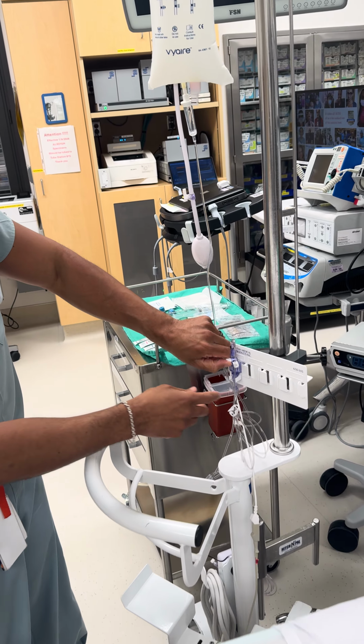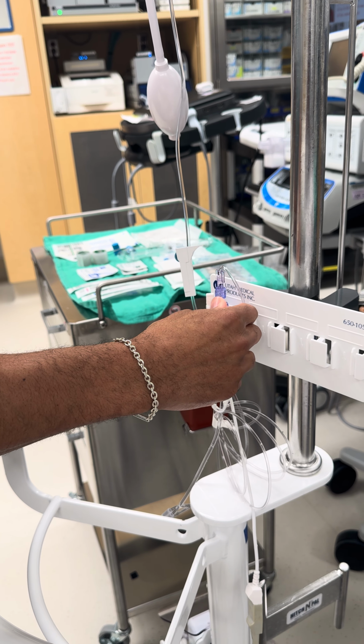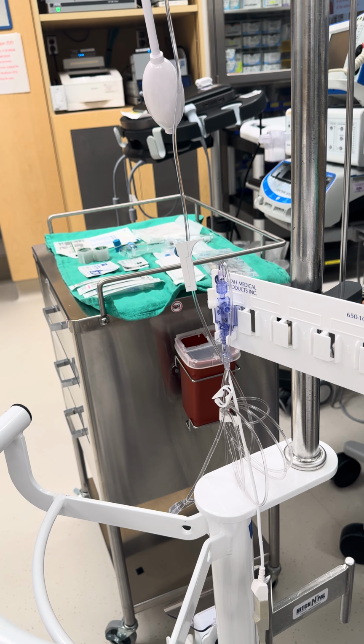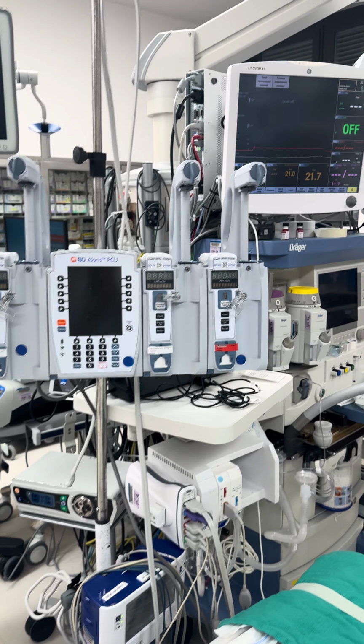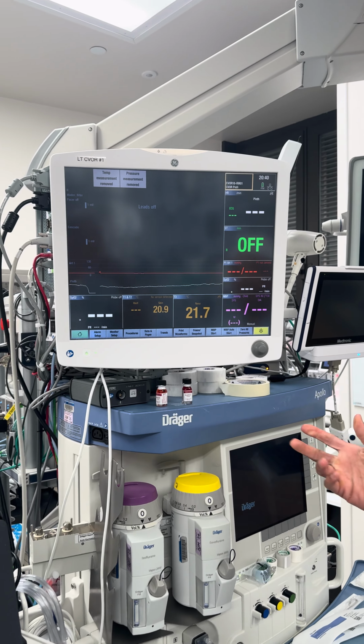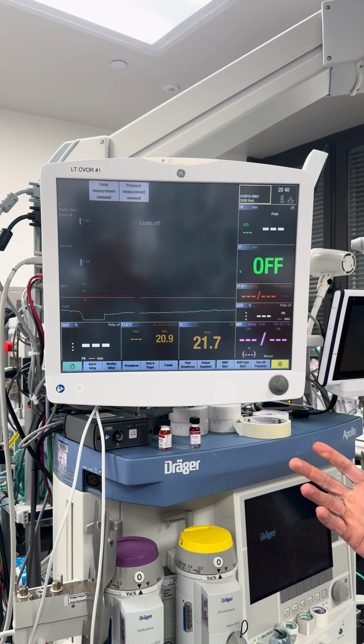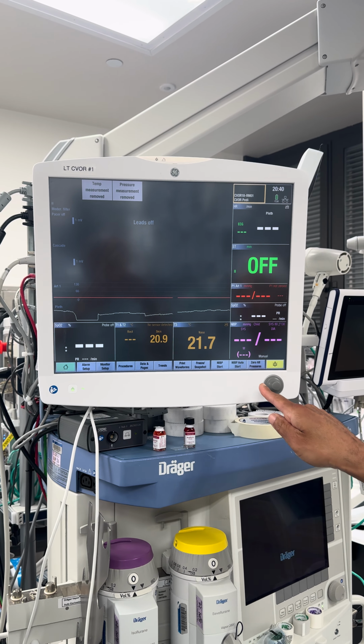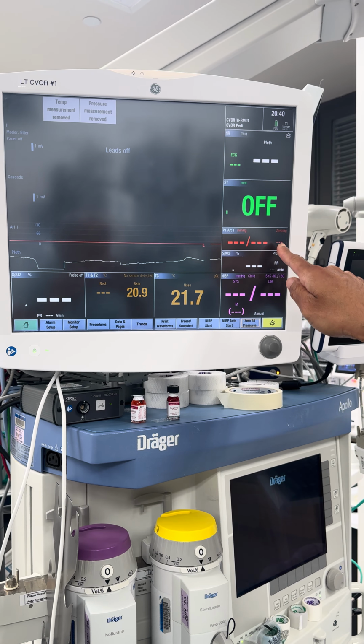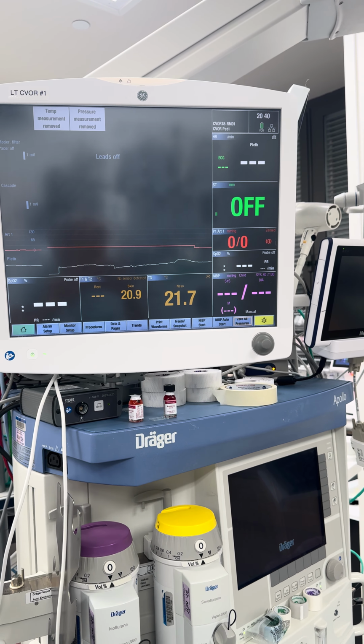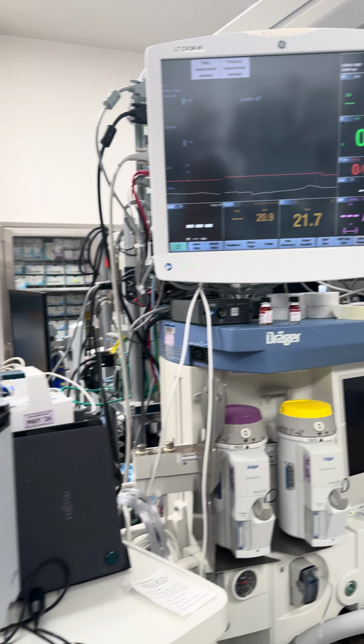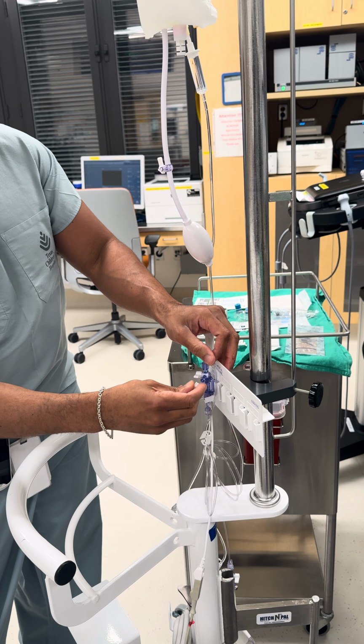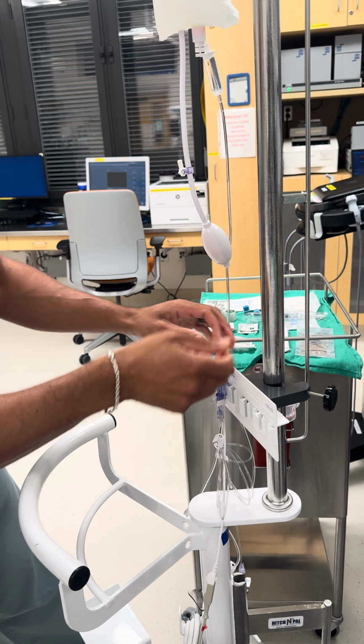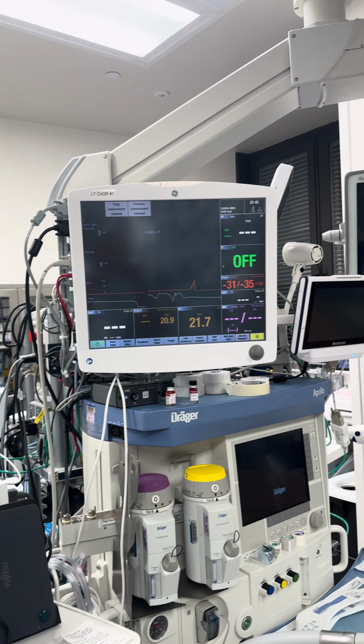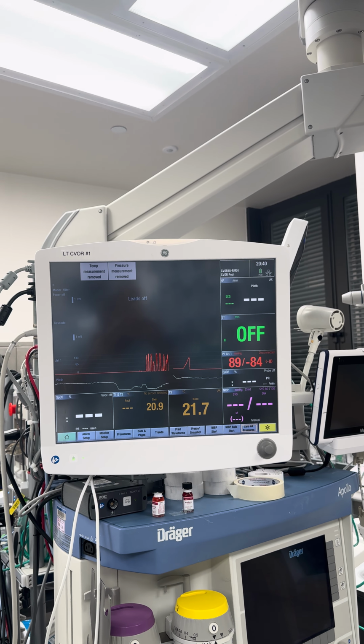So what you're going to do is turn this off to the patient, take off the cap so it's exposed to atmospheric air. You would come around to your monitor. And like I said before, this may be different from the facility that you're in, but the process is the same. You would go to zero all pressures, it says zeroing, it's zeroed. Now I have to go back over to my transducer, turn this back on to the patient. So I would flip the toggle switch of the stopcock, put the cap back on, and if you look, you'll see a waveform up there. And how we verify is we're just gonna move this up and down, and you'll see the waveform.